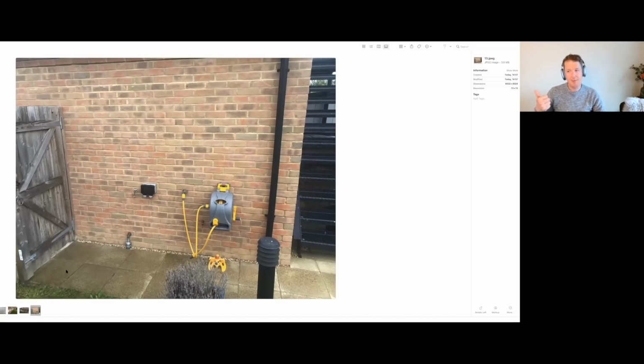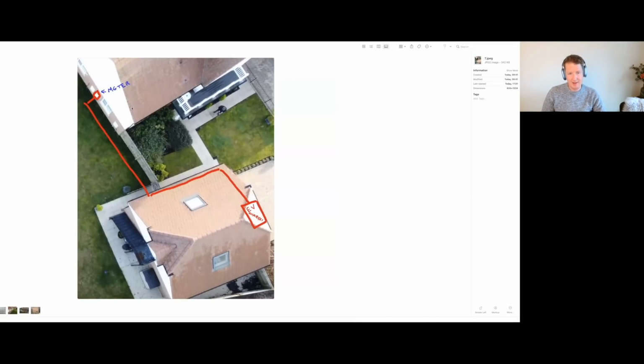We need grid limit, so we're going to have to hardwire the CTs as well, because we've got quite a distance here from the house to here — it could be 15 meters at least. I don't know whether the signal from the wireless CT unit that MyEnergi provides, the Harvi, will reach to there, and I don't want to risk it not working.